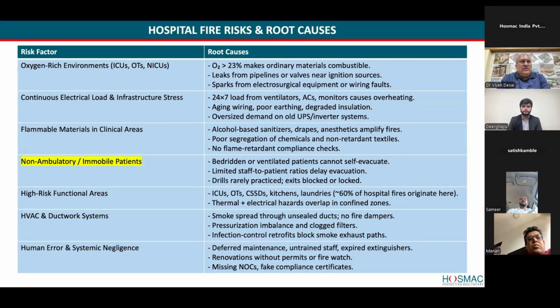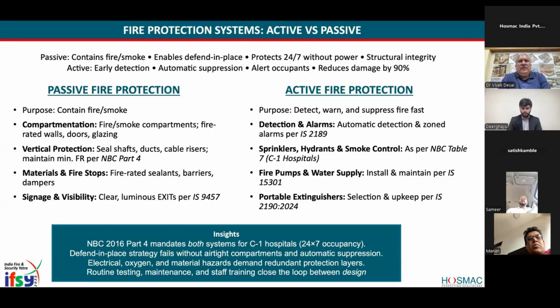Then missing NOCs, there are fake compliance certificates. This is something that we have to take upon ourselves not to indulge in, something which is wrong. All right. Then, fire protection system wise, there are two strategies that one has, passive fire protection and active fire protection. Passive means it contains the fire and smoke. What Satish was mentioning enables defense in place, in terms of the sprinkler, it protects 24/7 without power. Structural integrity is important, so the fire rating of walls and glass and other things is important.